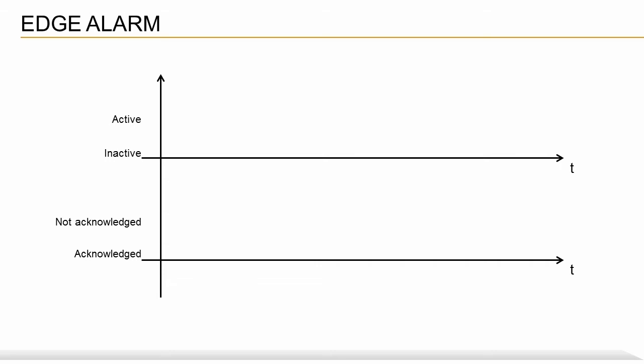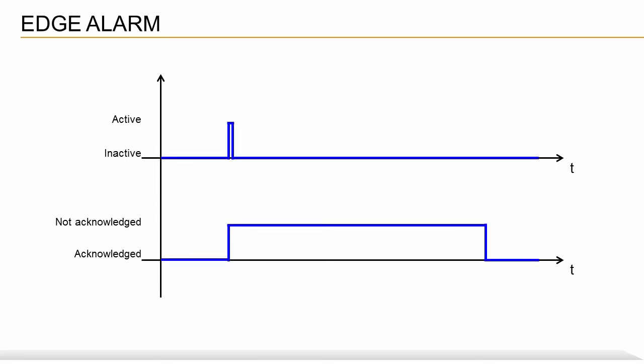Edge alarms are short-term alarms. You can think of them like an event. As soon as they are set, they are automatically reset. Examples of edge alarms would be things like, Recipe could not be loaded, or Message could not be sent. The alarm can then be acknowledged via either the HMI application or the control application.